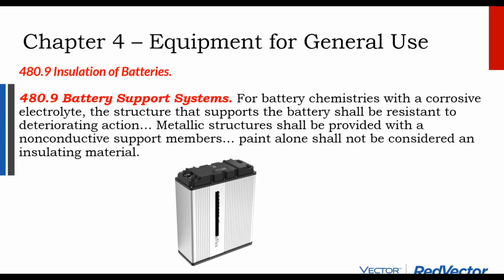So the takeaway here is that metal racks for batteries are not good enough. The racks have to have some insulative properties. What's interesting is that concrete is considered to be conductive, in the sense that if you have a concrete slab or a concrete wall in a basement, when it rains and the soil around it gets wet, the concrete itself gets wet and it can become conductive in those circumstances. Likewise, you can have some voltage creep out of a battery, and if it is on a metal rack, potentially the rack can be energized and that is a safety hazard.